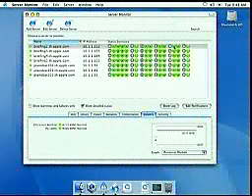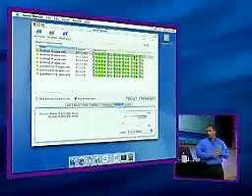And these things are hot swappable. I can open up the unit, let's say a fan's gone down, and in 20 seconds change out the fan without a single screw to replace, slide it back in without having turned it off. So if I get a warning, I can do something about it without bringing the service down to my customers. So very, very simple capability.